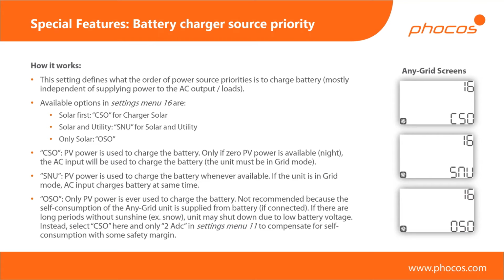Now here we're talking about the battery charger source priority. This setting is a bit different, in that it is not how we're powering our loads directly. This is how we decide to charge our battery. For example, we might purposely not want to use the grid to charge our battery, because then we're just shuffling around power. We might use only PV to charge our battery, because the battery is only supposed to be a buffer for the solar energy that we're consuming. So this setting is more or less independent from the previous setting.